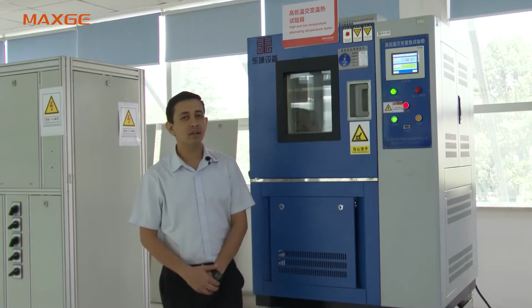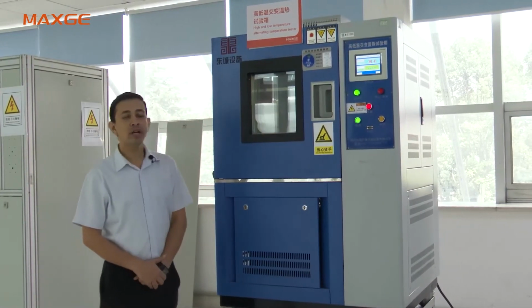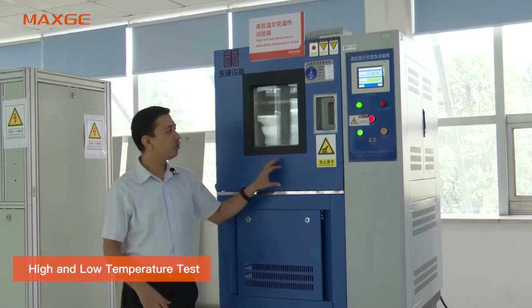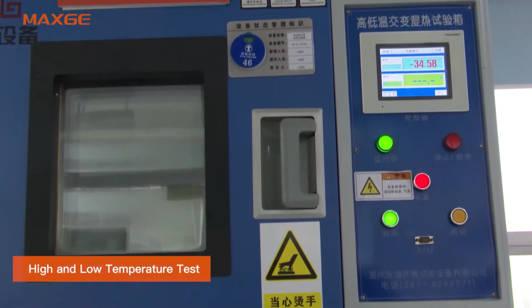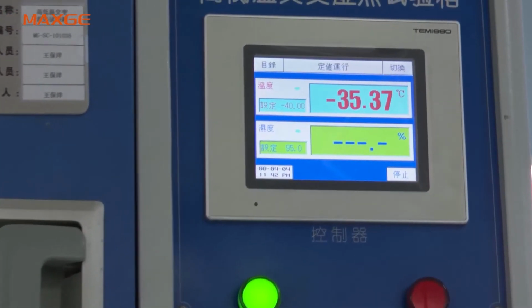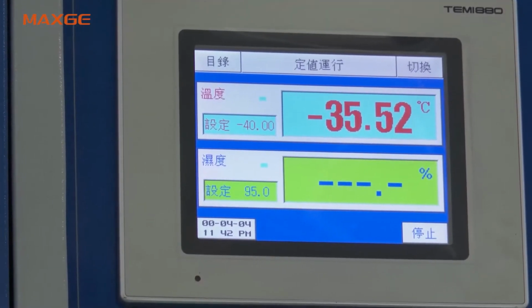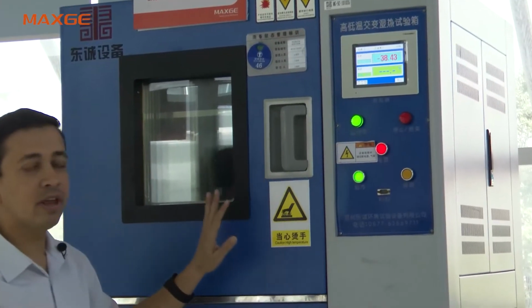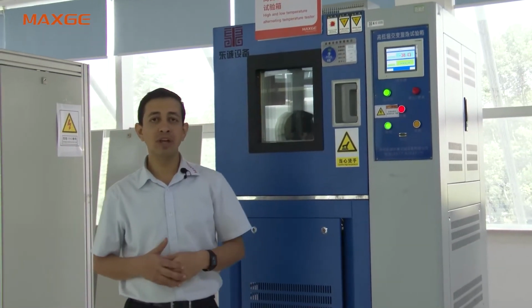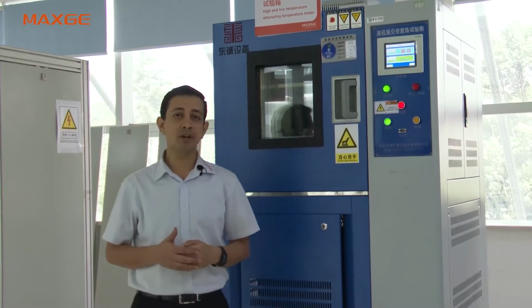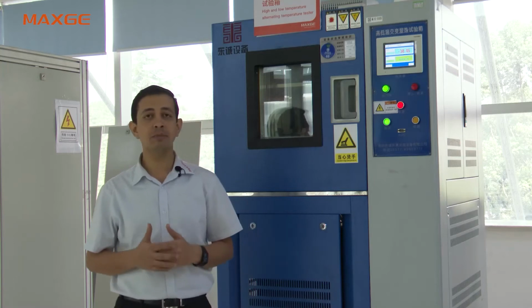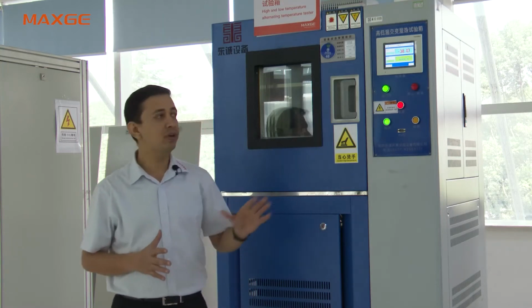Now we are standing at the high and low alternating temperature tester. Inside this chamber, you can see the temperature is being set at -40 degrees centigrade and the relative humidity is around 95 percent. So this test is performed at very high or extremely low temperature. Why do we perform this test? Because our MCBs are installed at various locations across the globe where the temperature is at a very high or very low level. So the performance of the MCB or MCCB should remain stable in those conditions. That's why we use this test.